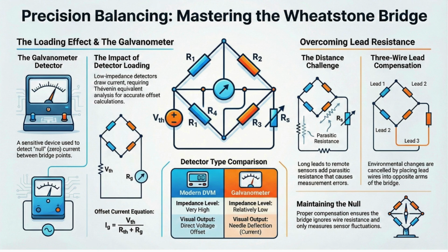Okay, speaking of dragging things down, let's talk about wires. The text brings up the long wire problem. Yes. The bane of instrumentation. Because your sensor is never sitting right on the circuit board, is it? It's out on a pipe maybe 100 meters away. Exactly. And copper wire has resistance. It might only be a few ohms, but it's there. You run wire out to a sensor and back, you've just added 5 or 6 ohms to that leg of the bridge. And the bridge doesn't know the difference. It just sees total resistance.